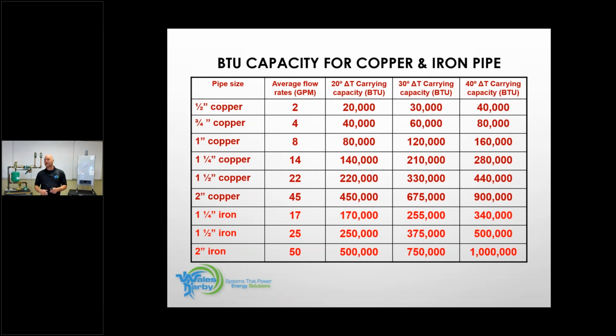Jim has a question. Yeah, good question here. When would you use a 30 or a 40-degree delta T? When would you design a system that way? Okay, so I'm a fan of designing a condensing product at a 30-degree delta, and I may only do the boiler circuit at a 30-degree delta and then do the system circuit at a 20.